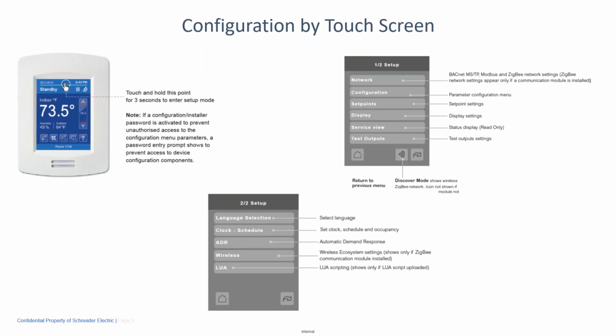I mentioned a couple times that these are configurable devices. How do you configure them? Basically, you touch and hold at the top center part of the screen, and it takes you to 2 pages of setup. Each one of those setups has menus for whatever function you're trying to set up. So network functionality sets up for the BACnet MSTP, the Modbus, the Wi-Fi, or the Zigbee communication protocol.